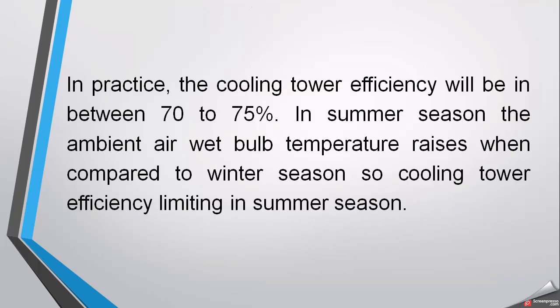In practice, cooling tower efficiency is typically between 70 to 75 percent. In summer, the ambient wet bulb temperature rises compared to winter, which limits cooling tower efficiency. Because temperatures — especially wet bulb temperature — are higher in summer, the cooling tower efficiency is more constrained in summer than in winter, meaning maximum efficiency is harder to achieve during the hot season.